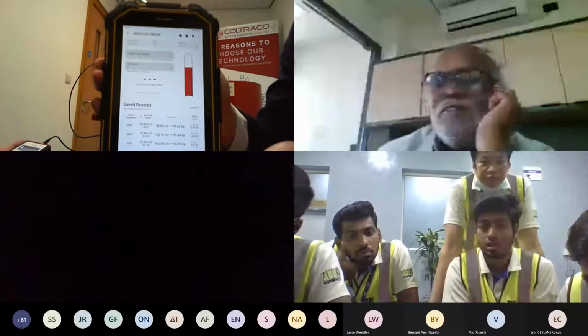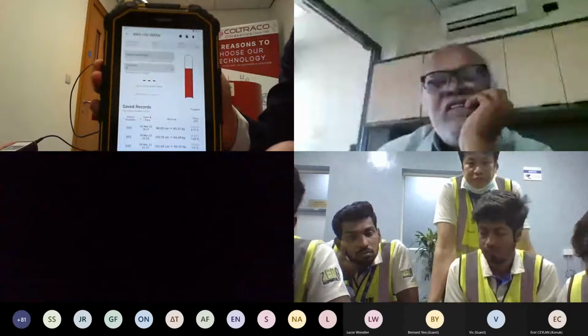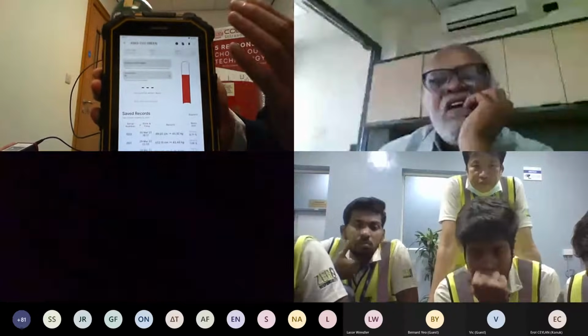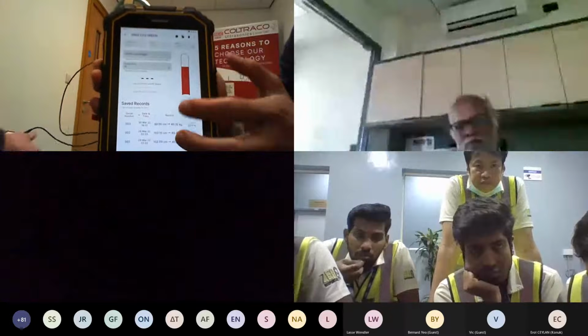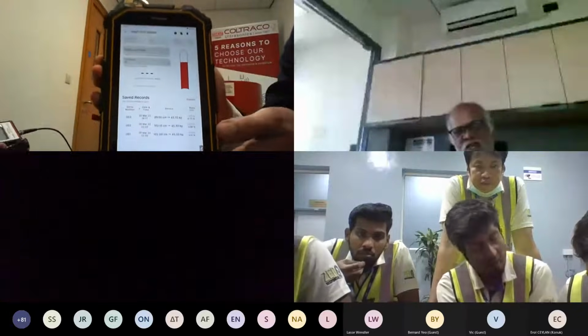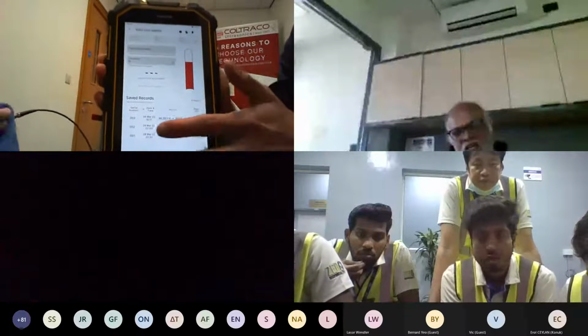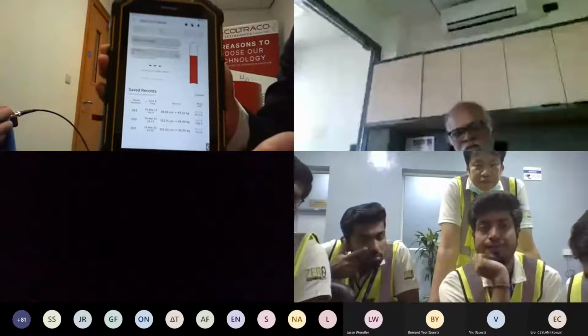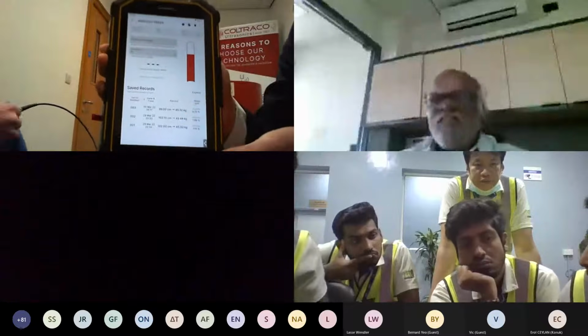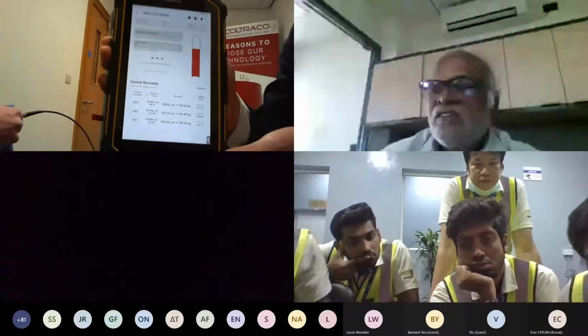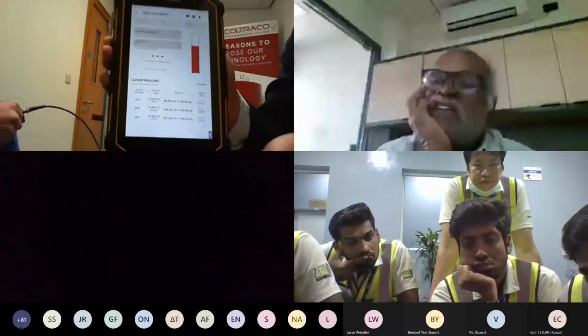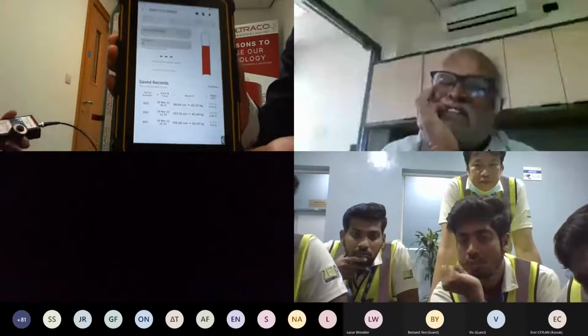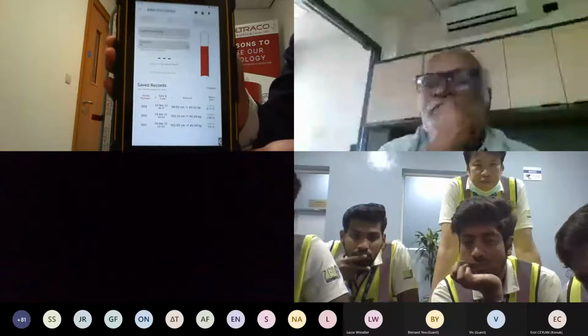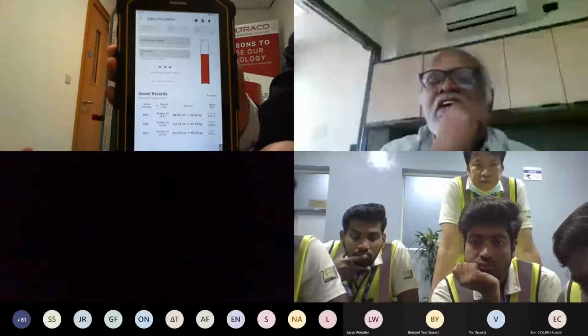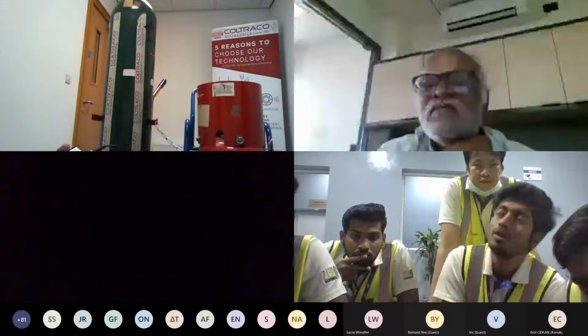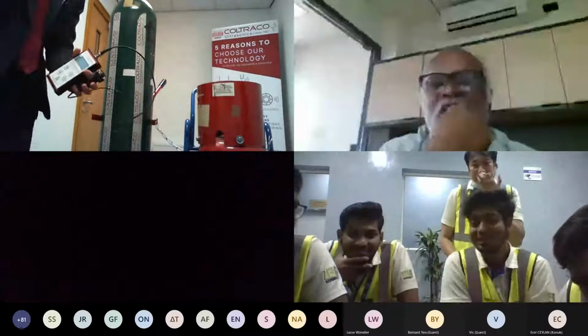So this device allows your servicing technicians to inspect a fire suppression cylinder, to save the result in weight, and also enables you to export it based on these Portasteel tablet. The record comes with a date and time stamp, so you know exactly when the test has been done and you can export it. These date and time stamp are unchangeable, so you know that when you've done the measurement, it's actually there at that time. It allows for better traceability of your test processes. So this is the Portasteel tablet. And Benjamin, I think we'll move on to the next cylinder. Thank you. Thank you, Adrian.